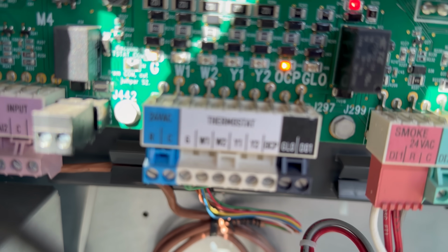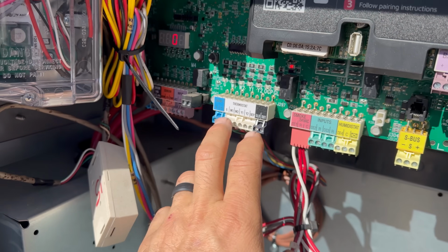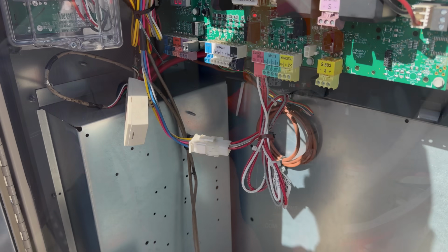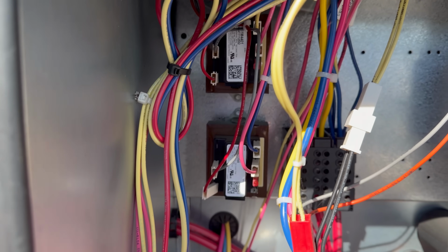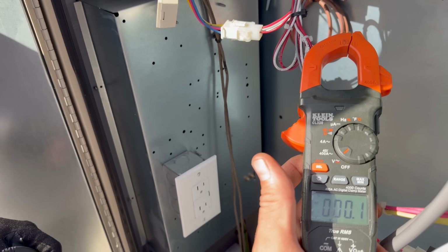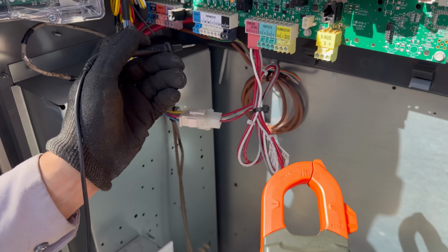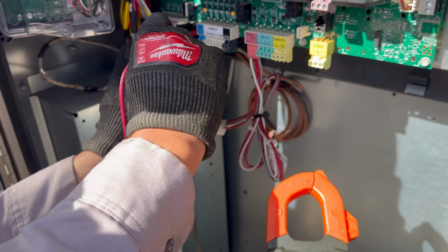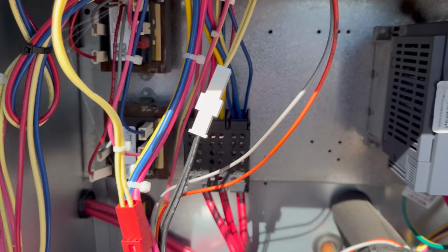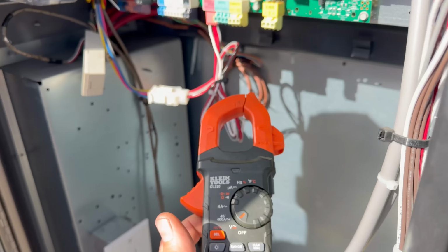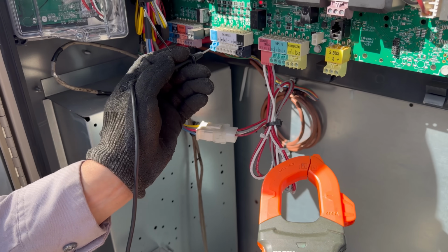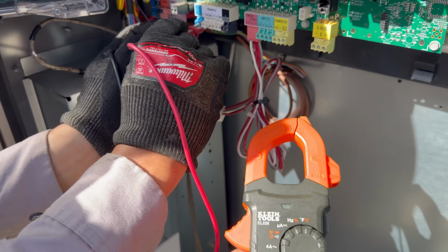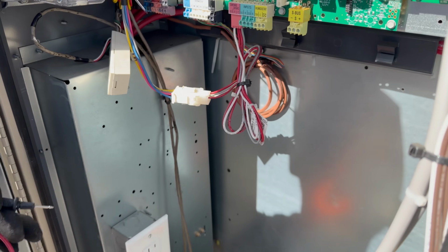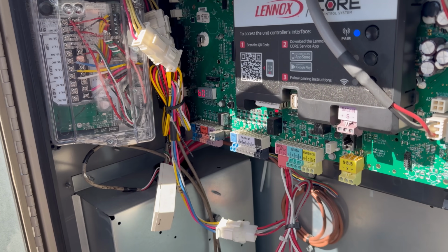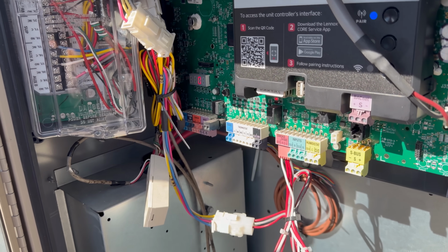Well, let's start at the connections right here. So we're going to check between R and C to make sure we have 24 volts. Okay, so the transformer, which is one of these two, is sending power downstairs. So now we need to check from C to G and prove that the thermostat is telling our blower to run, and it is, of which the VFD is at 60 hertz. Okay, so now check between C and Y1. We got nothing. Okay, at this point, that's a problem with the thermostat. The thermostat is not calling or something's happening.